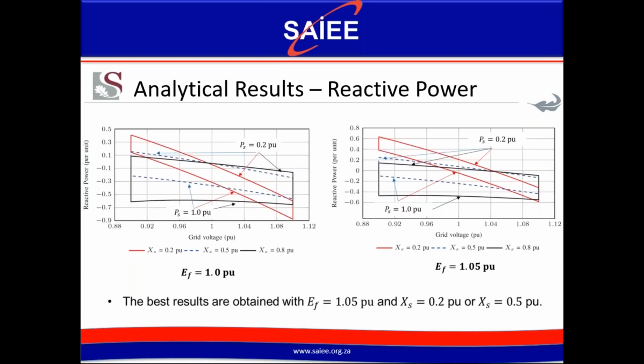The slide shows the analytical results for the reactive power versus grid voltage and supply power for the same 3 considered synchronous reactance values in the same 2 scenarios of back EMF voltage. However, for these curves, the top portion of the curves indicate where the supply power was kept constant at 0.2 per unit, and the bottom portion of the curves indicate where the supply power was kept constant at 1 per unit. As can be seen, the best results are obtained for a back EMF voltage of 1.05 per unit and a synchronous reactance of either 0.2 per unit or 0.5 per unit.